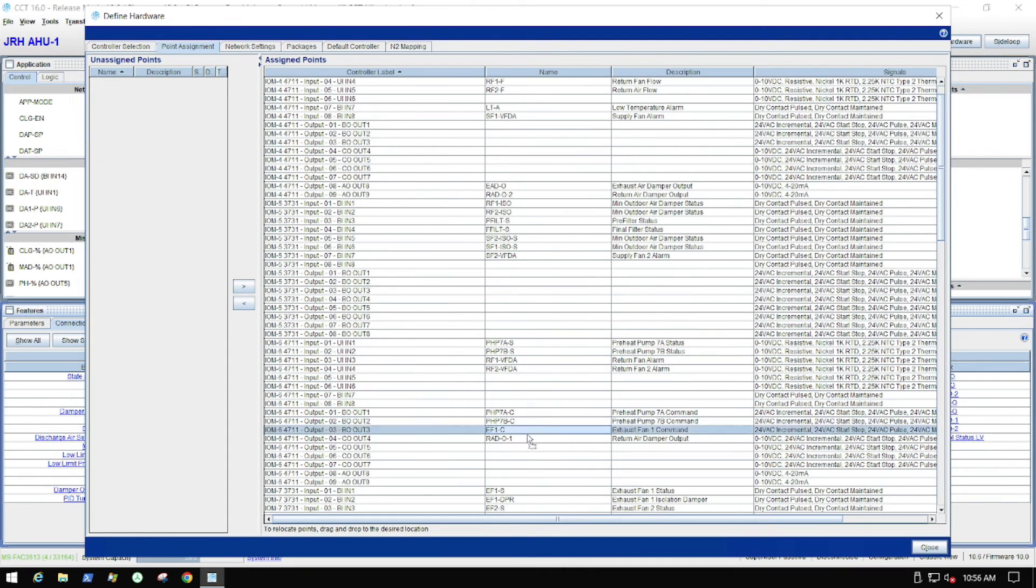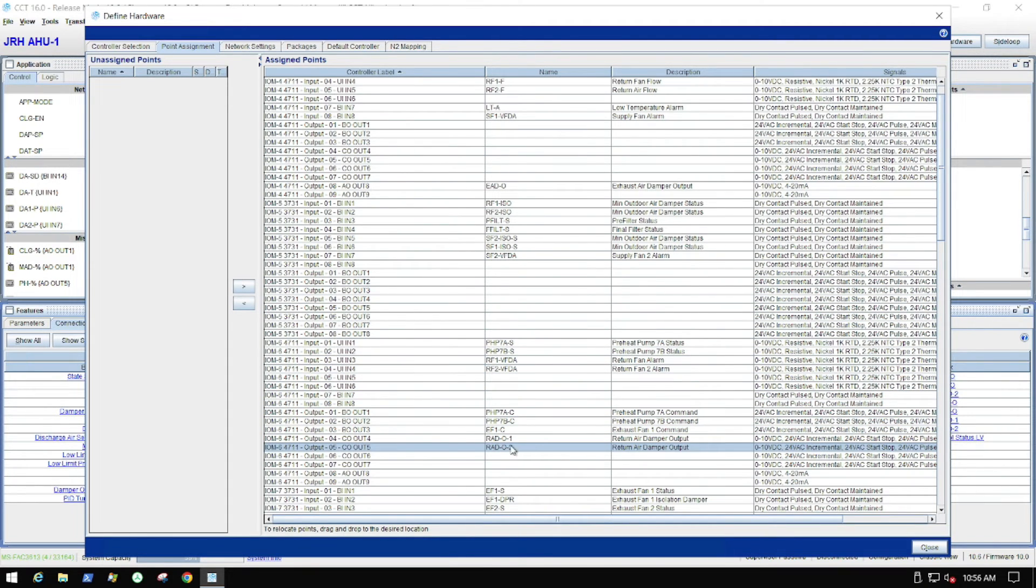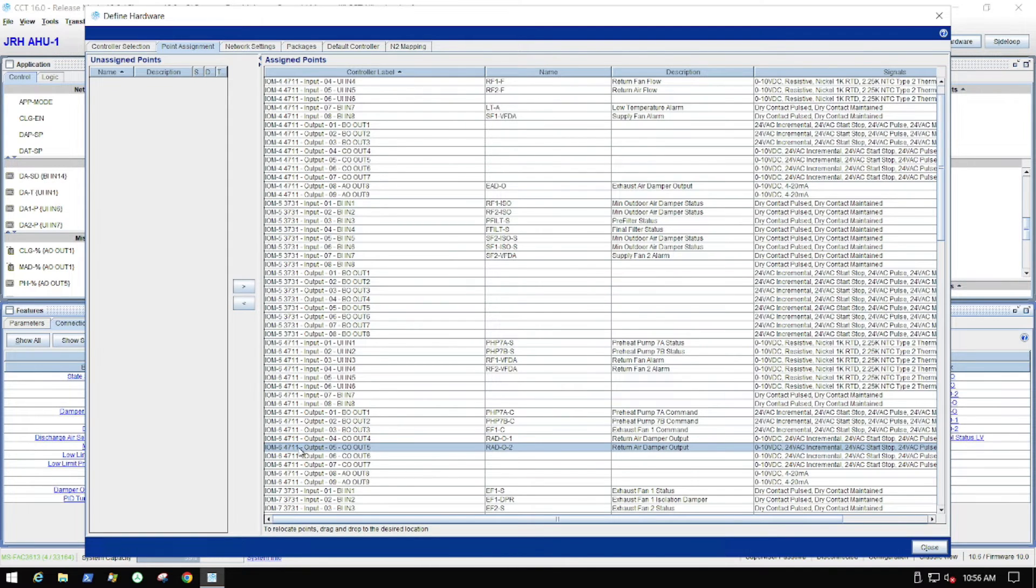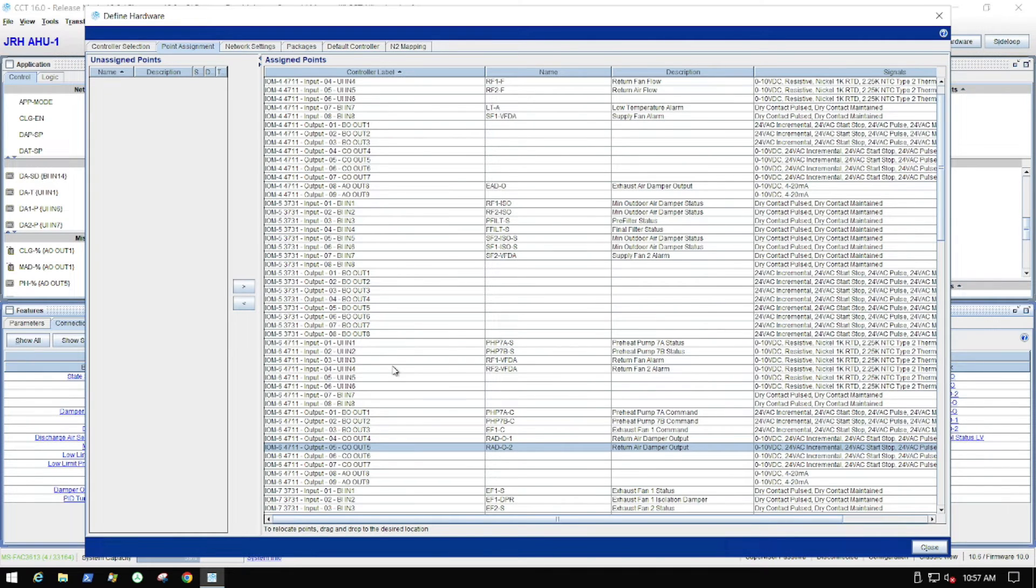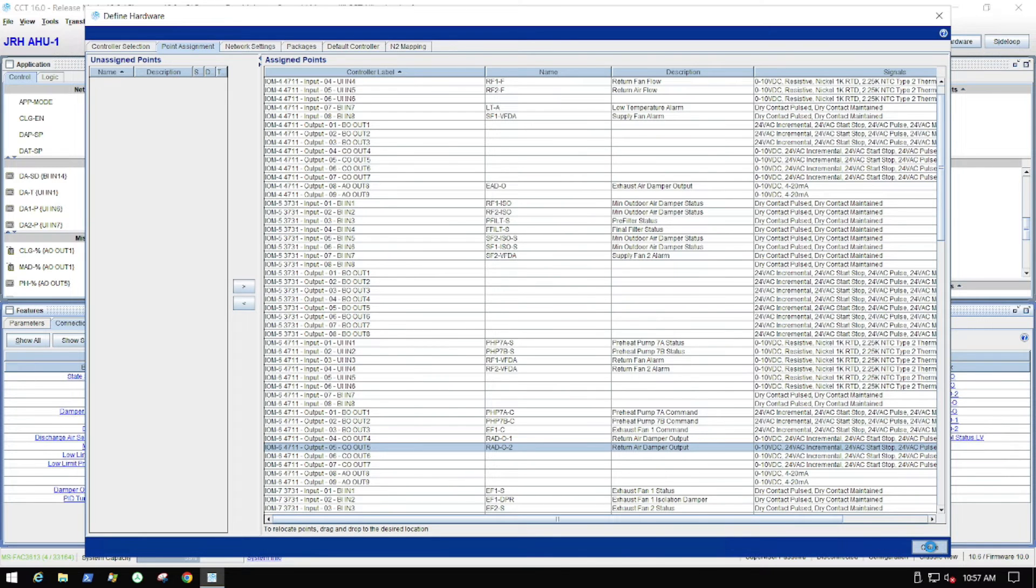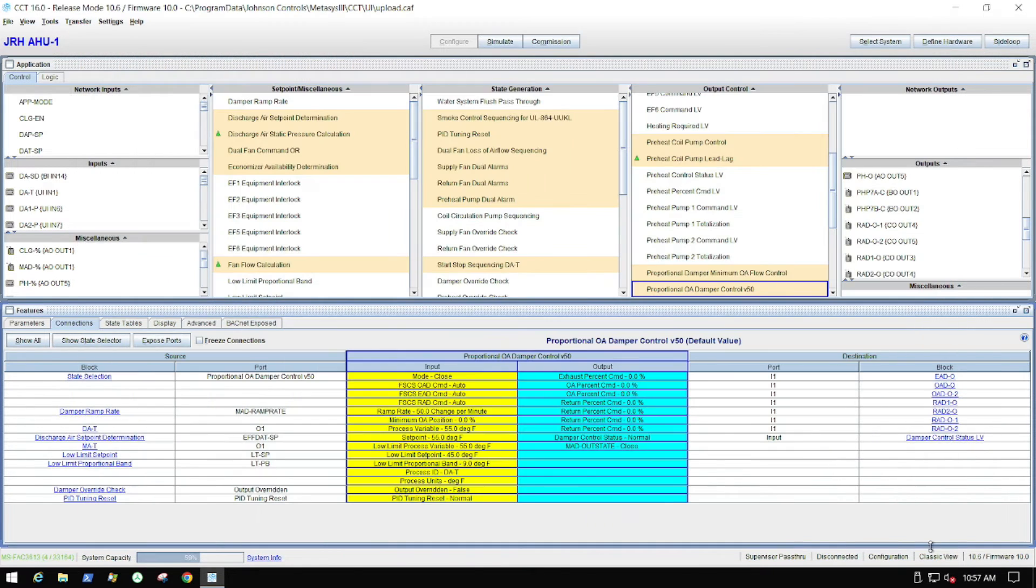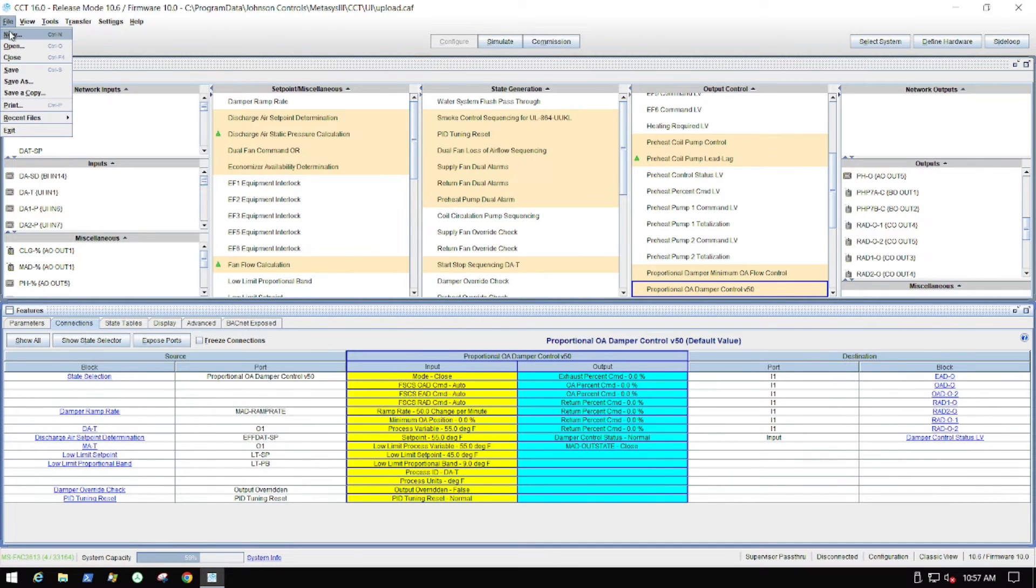Now that I've got my second point, I'm dragging it down to the output, the physical point, where I need it to be. Again, it's much easier to run a communication cable than it is a whole bunch of physical control cables, which, you know, with the points count and things like that, we would have had to add additional I.O. as well, even if we didn't do this.